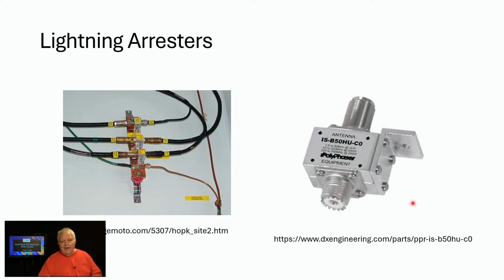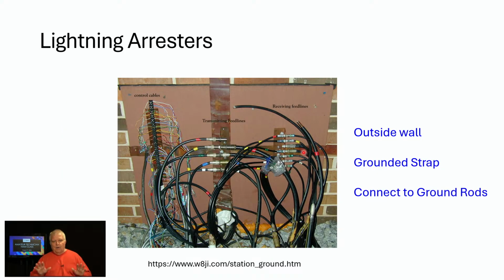In some cases you can't disconnect the antennas readily, so we use what are known as lightning arresters. These are devices from Polyphaser or Alpha Delta or other manufacturers. The antenna transmission line connects here, and your radio equipment on the other side. This provides a way to bond and ground, with an element inside that will short out should there be a high voltage spike. You want to install these on the outside of your ham shack, on an outside wall, to a grounded plate or flat copper strap connected to one or more ground rods below. These lightning arresters are highly recommended for antenna connections on your amateur radio gear.